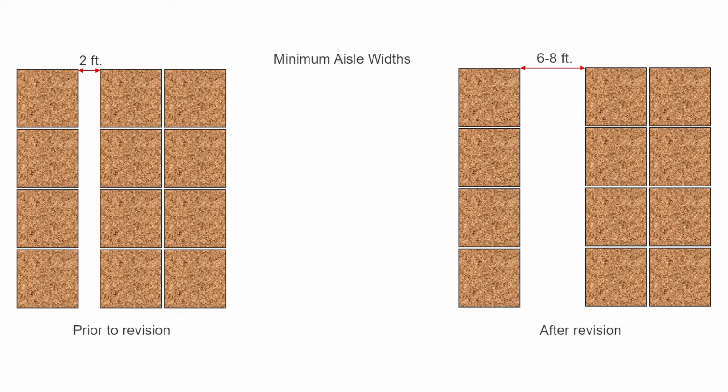So the significance of losing it in tables 2 through 11 and going over to 17B is that 17B has very specific aisle requirements. For the K22, K25 and K28 for the 50-foot application, also the K33, it has a 6-foot aisle limitation. So the first thing is there's a gap that we don't have multiple row in table 17B as of yet.